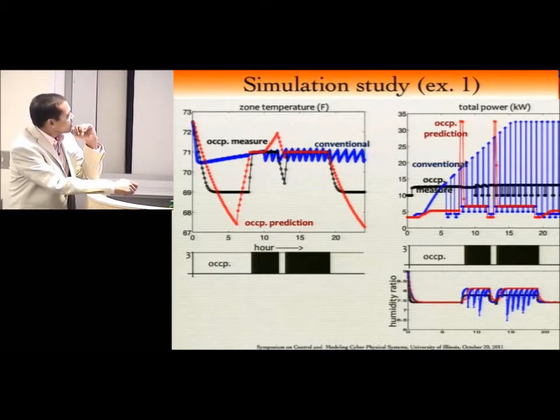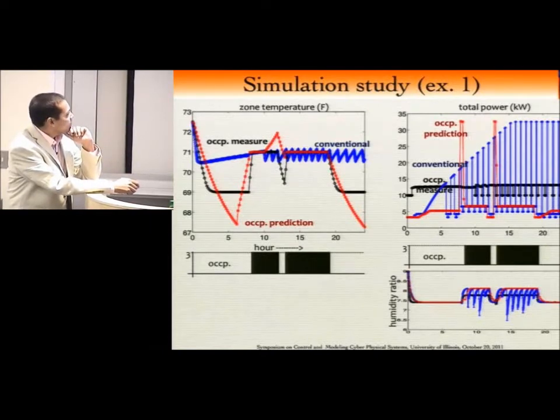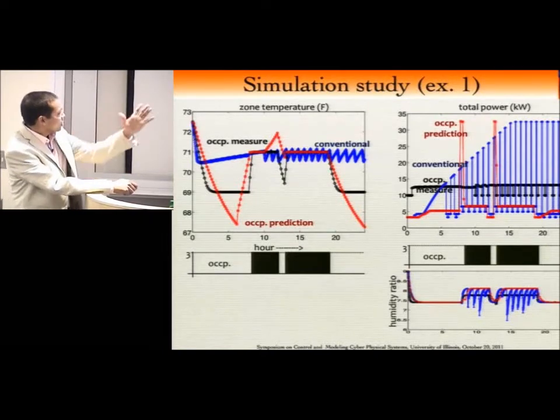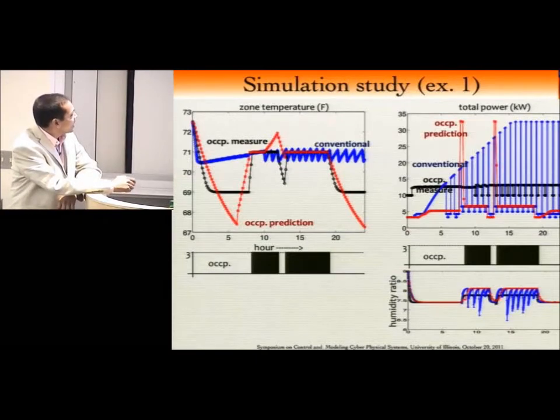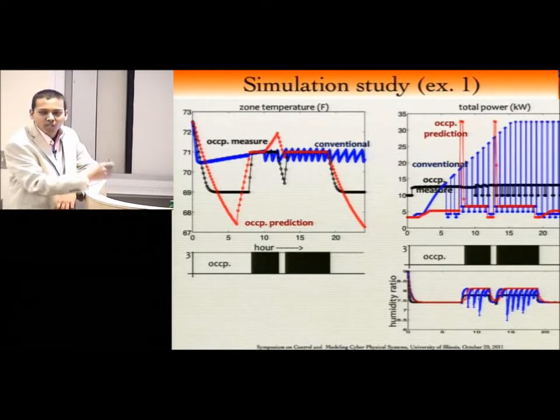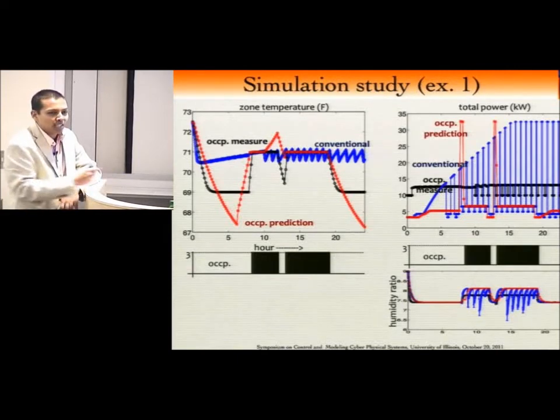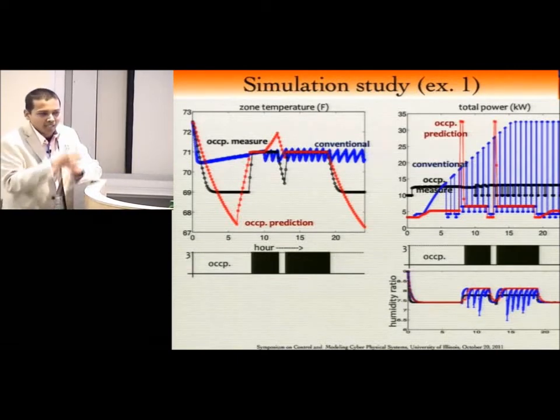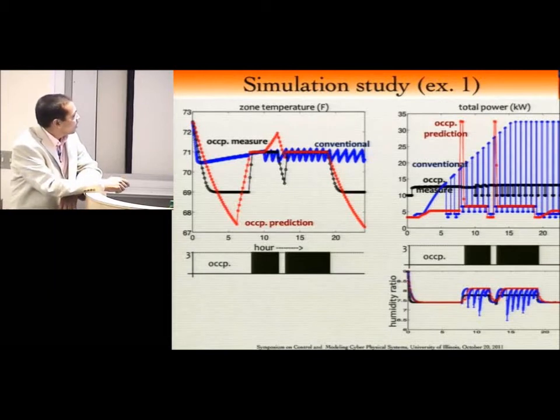The red one is the same sort of controller, except in this case we assume that we have perfect occupancy prediction. I don't know where it comes from. Let's assume the best case scenario, somehow I have perfect occupancy prediction. If I have that sort of long-term good prediction, it will let the temperature float as close to the supply air temperature, 55, until about 20 minutes before it knows occupants are going to come in. At that time, it's going to ramp up just in time to meet the deadline when the occupants come in. All right.